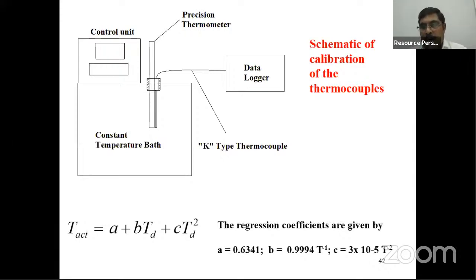Then you make a plot between your thermocouple standard input - meaning the input set by the thermostatic bath - and the output of the thermocouple. So you present the characteristics, and from the characteristics you can get this equation: T actual equals A plus B into TD plus C into TD squared, where TD is the temperature shown by the thermocouple.